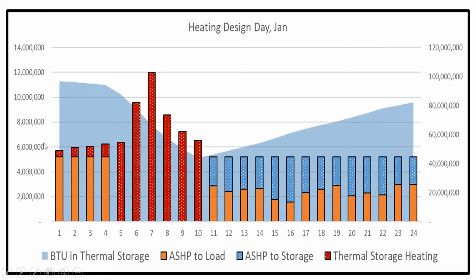On the left-hand scale, we're looking at the load profile of the building. So the red is meeting the absolute hourly load profile of the building. The orange is also the heating load profile of the building. And what we have here is a building that has a peak of about 12 million BTUs, but we put in a heat pump that has about 5.5 million BTUs of capacity. And during the day, when the heat pump's running, it is meeting the load, and it's melting some ice. So that's the blue bars. And you're putting energy into storage. So you can see the storage inventory growing.